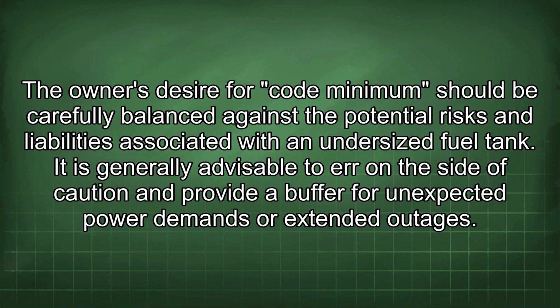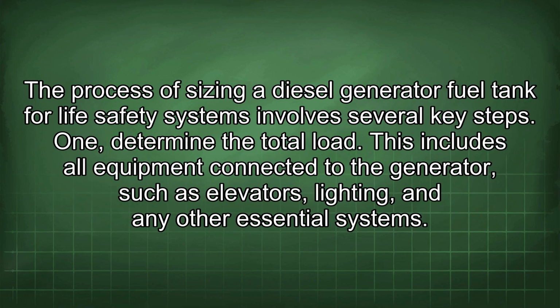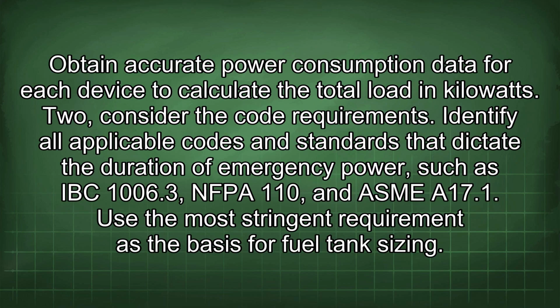demands or extended outages. The process of sizing a diesel generator fuel tank for life safety systems involves several key steps. 1. Determine the total load. This includes all equipment connected to the generator, such as elevators, lighting, and any other essential systems. Obtain accurate power consumption data for each device to calculate the total load in kilowatts.